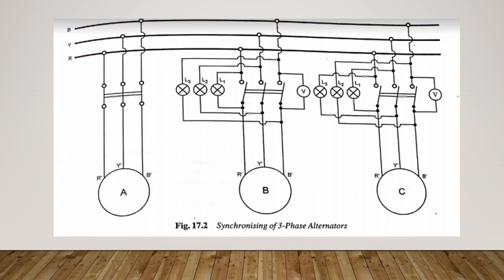The speed of the prime mover of the incoming machine will be further adjusted until the lamps flicker at a very low rate, and the voltage of the incoming machine is again adjusted to be equal to that of the running generator or bus bars. The paralleling switch will be closed at the instant all the three lamps are dark. The major disadvantage of this method is that lamps will go dark at somewhat less than half their rated voltage, and so the paralleling switch might be closed when there is a considerable phase difference between the machines, with a high circulating current resulting in possible damage to the machine. Another disadvantage is that the lamp filaments might burn out.